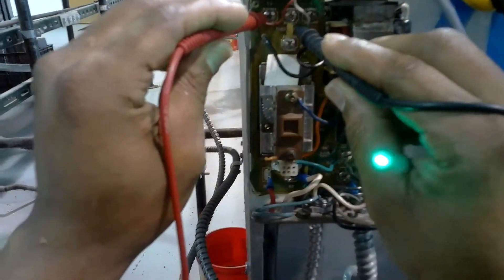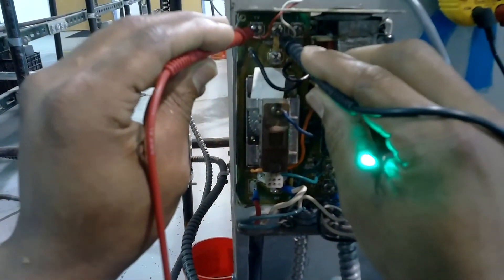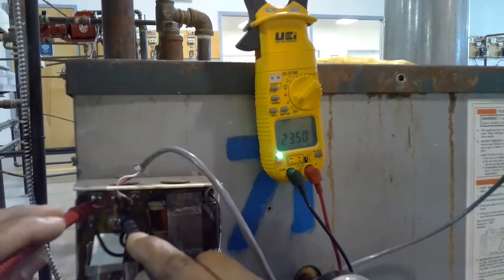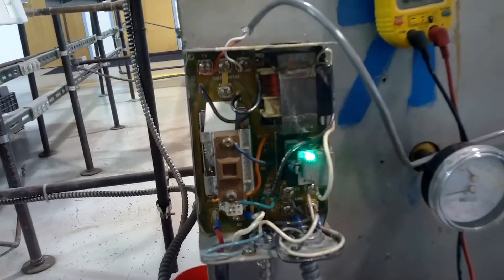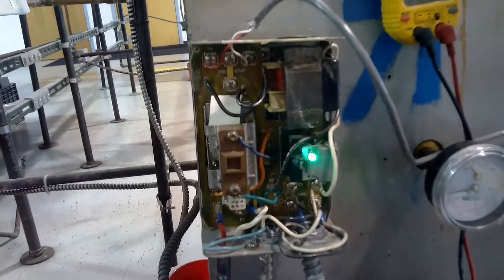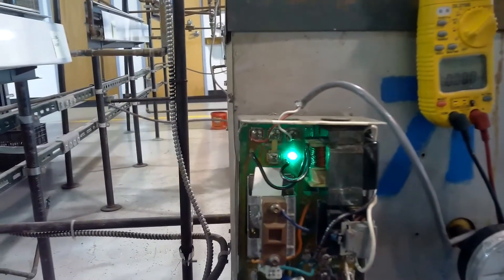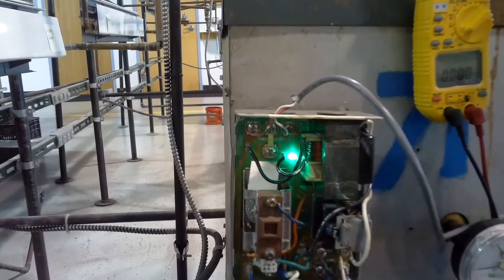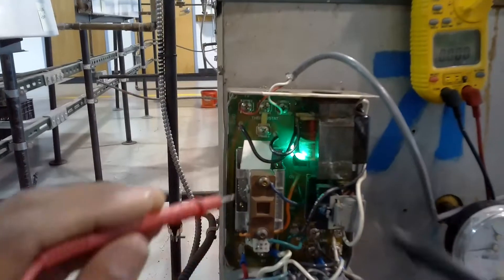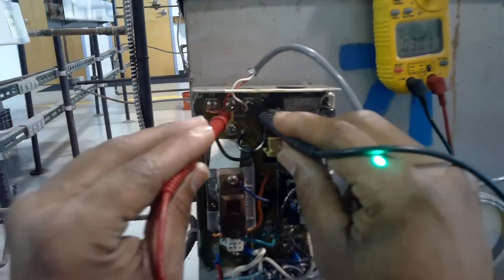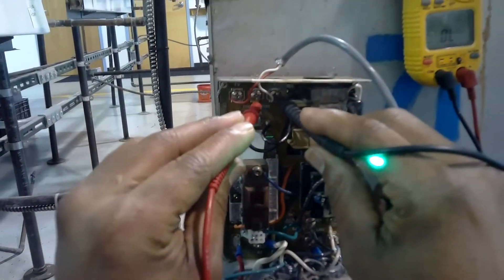I'll use the W for my common. I have 23 volts. Now I'm going to check 24 volts coming back from my thermostat going to my aquastat T and W.